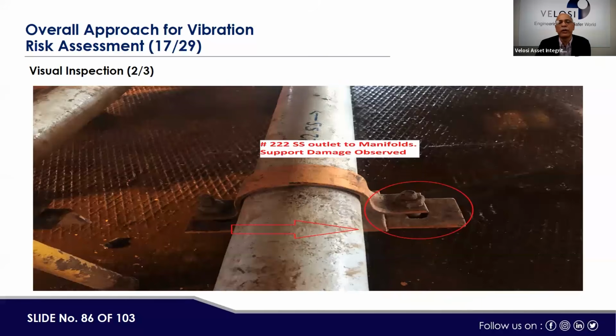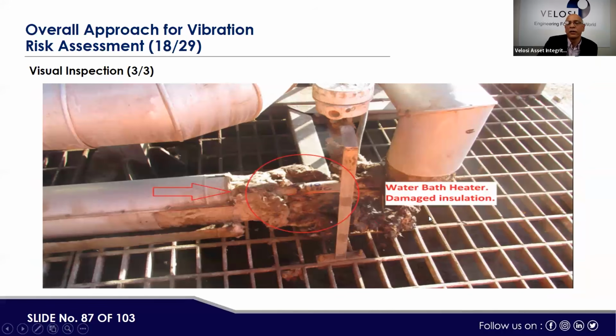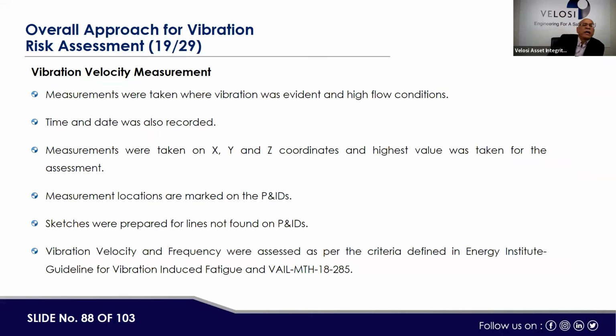Here, outlet to the manifold support damage was observed, and practically it may not be effective or may not be controlling. Here, water bath heater insulation damage, if insulation is damaged due to whatever reasons, and there are some vibrations as well. Now, the next part is the vibration velocity measurement.